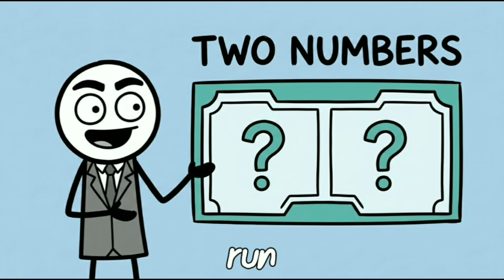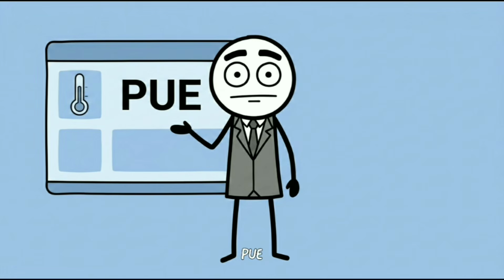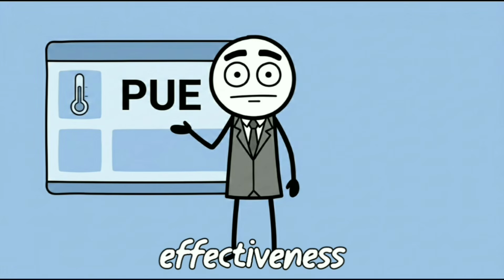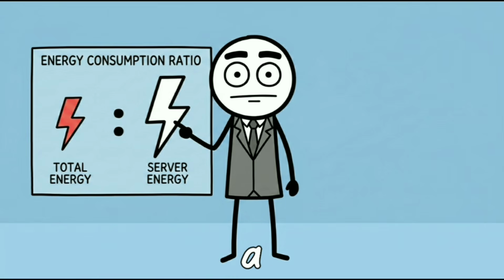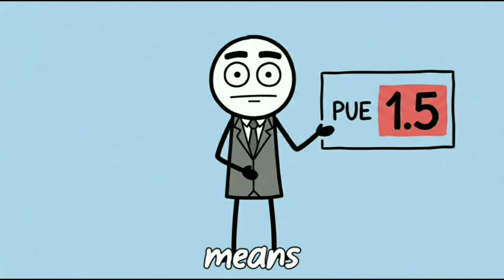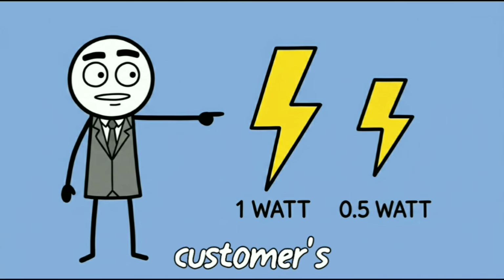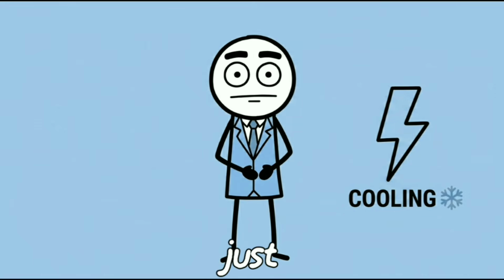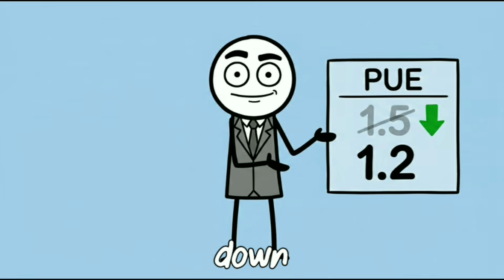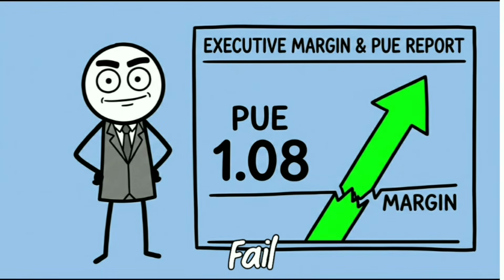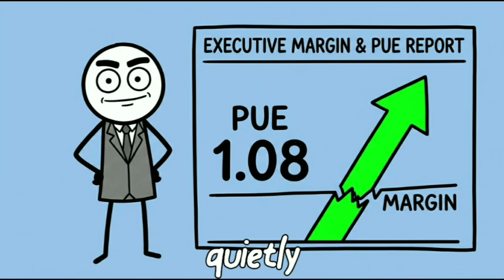Two numbers actually run this entire business. The first is PUE, power usage effectiveness. It's the ratio of total energy a facility burns against the energy that actually reaches the servers doing useful work. A PUE of 1.5 means for every watt powering a customer's equipment, you're burning another half watt just keeping the building cool. Shave that number down toward 1.2 or lower, and you're printing margin out of thin air year after year on a fixed physical footprint. Fail to shave it, and your electricity bill quietly eats every dollar of profit the leases were supposed to generate.